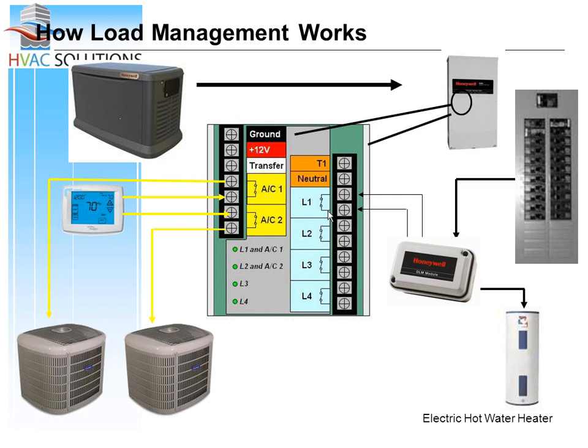So we're trying to keep a minimum of 60 hertz. And when we drop below, I believe the number is 55 hertz, we start shedding. So the minute that we're not able to produce clean power, it's going to shed because that generator is doing all it can do. So AC1 and L1 would come on, AC2 and L2, and then L3 and L4. So that's kind of the sequence of events.